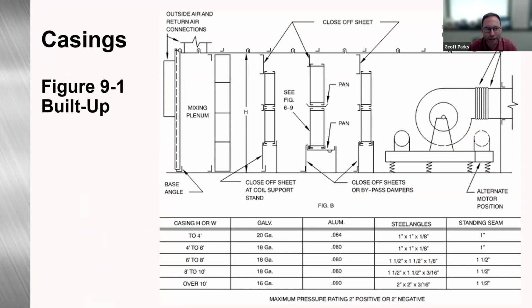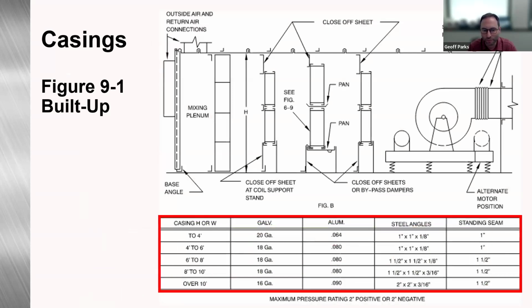So here we have figure 9-1, built up standing seam casing. Based on the casing width and height, there are some recommended minimum gauges for galvanized, or aluminum, which gives you your steel angle sizing and then your standing seam height. And this is only for a maximum pressure rating of 2-inch positive and 2-inch negative on this type of construction.